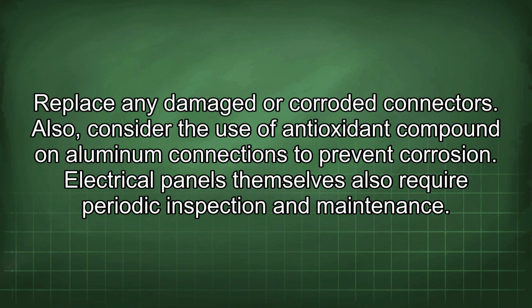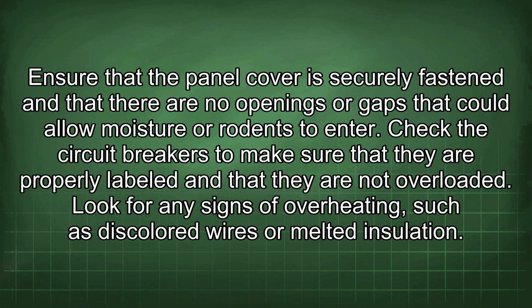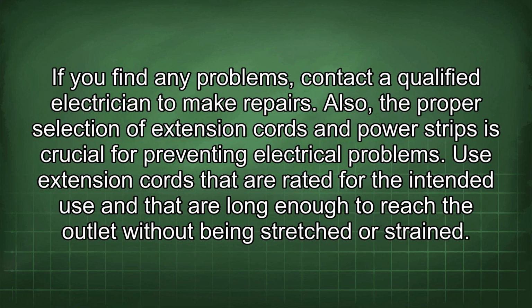Electrical panels themselves also require periodic inspection and maintenance. Ensure that the panel cover is securely fastened and that there are no openings or gaps that could allow moisture or rodents to enter. Check the circuit breakers to make sure that they are properly labeled and that they are not overloaded. Look for any signs of overheating, such as discolored wires or melted insulation. If you find any problems, contact a qualified electrician to make repairs.